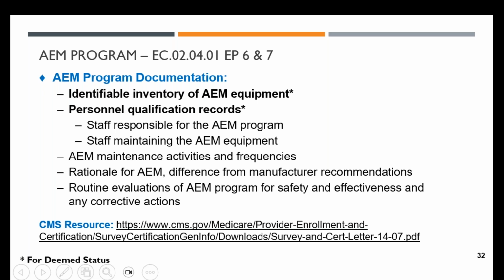You also need to make sure that, just like non-high risk and high risk on a PM, the AEM frequency is at 100% completion. And you need to have your rationale or justification for why you're putting a certain subset of equipment on an AEM. And lastly, you need to perform routine evaluations on your AEM. You know, don't not look at it for 5 or 10 years.